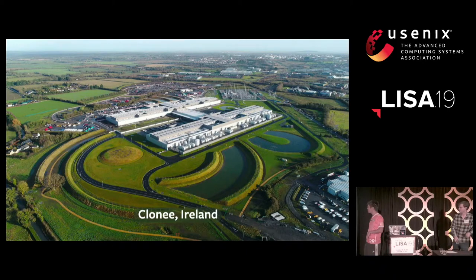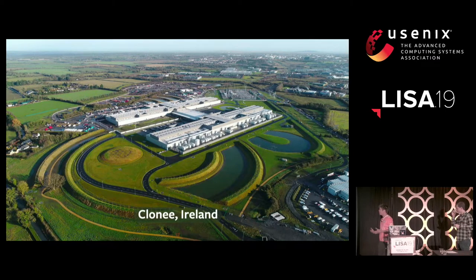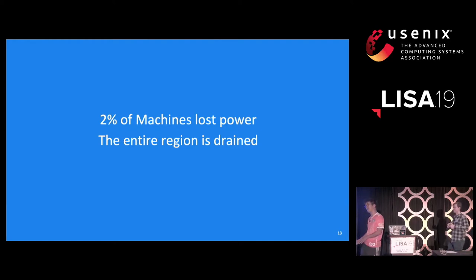Now let's look at what we call sub-region failures, where a part of a region actually fails. This is our data center region in Clonee, Ireland — it's got a few hundred thousand servers in it. One day recently we suffered an outage where a few thousand servers lost power, and we ended up draining the entire region. So we lost 2% of our servers within this huge facility, but we're going to leave the other 98% idle — what's going on?